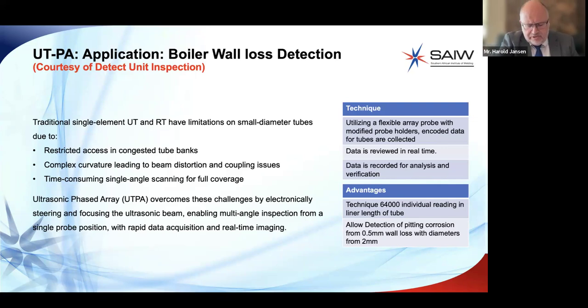Detect unit inspection utilizes a flexible array probe equipped with customized holders to identify a 0.5 millimeter wall loss in pitting corrosion of 2 millimeter diameter and bigger. Real-time data review is conducted to ensure that only accurate and accessible information is collected for subsequent analysis and reporting.